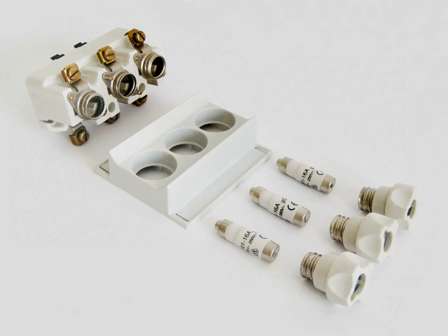The larger end cap, the bottom of the bottle, has at its center a small spring-loaded button retained by a thin wire, which serves as a fuse blown indicator. When the fuse blows, the wire breaks and the indicator button is ejected by the spring. A missing or displaced indicator thus pinpoints a blown fuse. The removable part of the fuse holder has a small window to allow inspection of the indicator without removal of the fuse. The indicator button usually has a colored dot indicating the fuse rating.